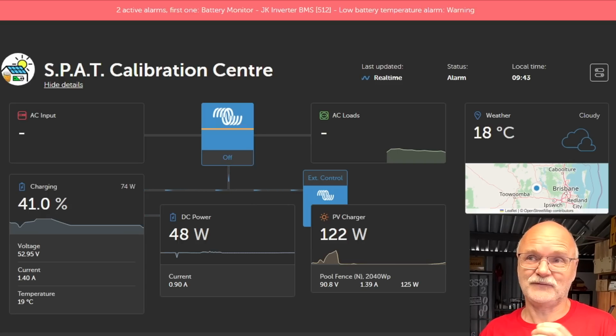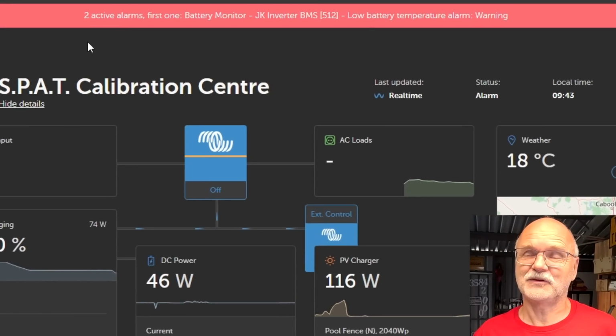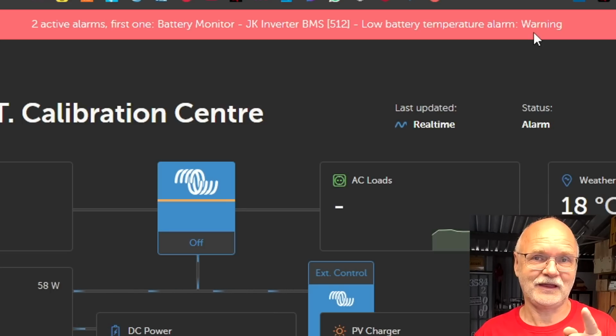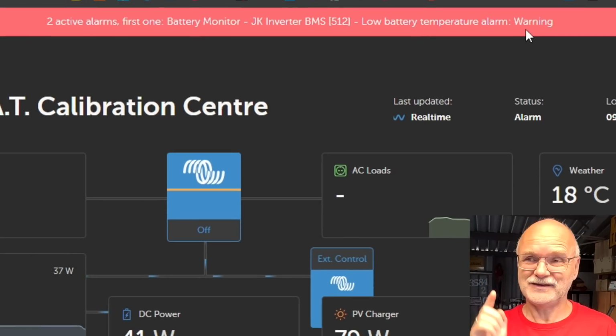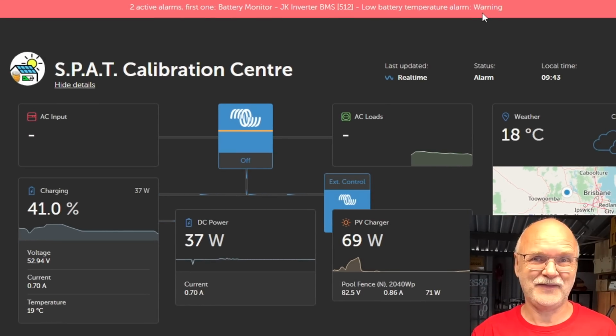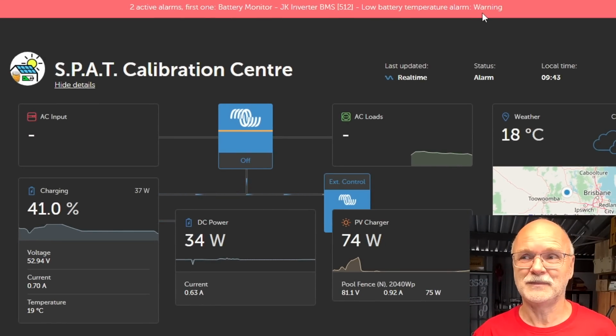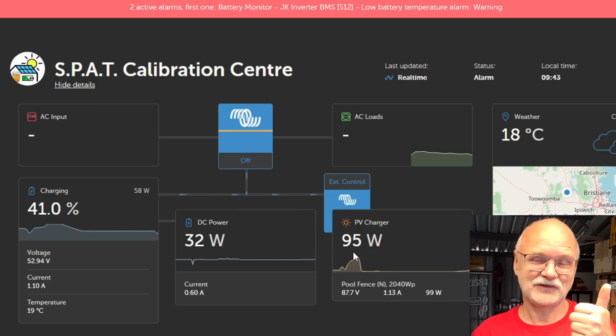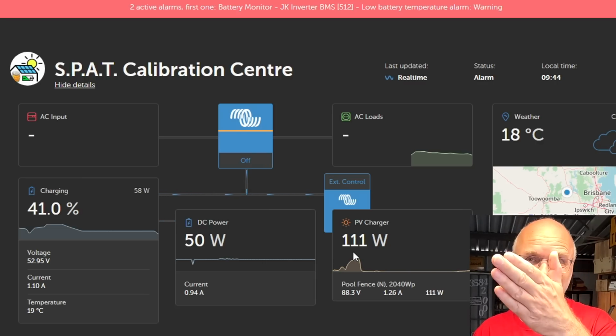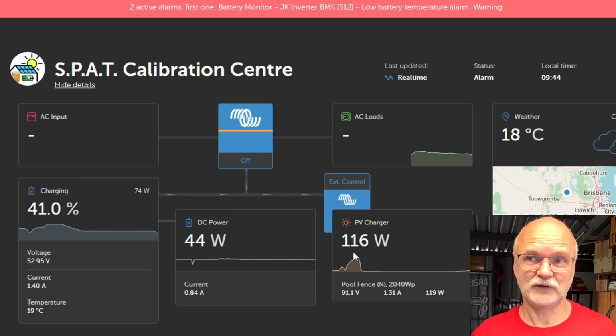So if we have a look at the Victron VRM, we can see here at the top we've got 2 active alarms. Battery monitor, JK Inverter BMS, low battery temperature alarm, warning it says, right? So now the system makes the user aware that there is something wrong with your system. As you can see, it is still charging, and it keeps continuing to charge as long as one battery is still not in any protection or warning state. But it notifies you now in the VRM on your mobile phone, push notifications.